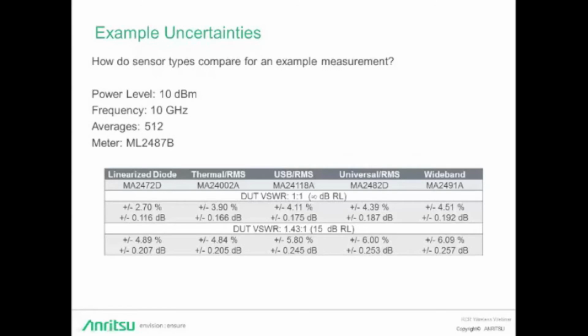Let's take the same setup that we had earlier. The table below shows MUs for our 5 different sensor types. The top half of the table shows MUs under ideal conditions where the sensor and the DUT are perfectly matched, and the bottom half shows MUs for a standing wave ratio of 1.43 to 1. A few observations from the table, again specific to this measurement configuration. A single diode or diode pair gives the lowest uncertainty under ideal conditions.